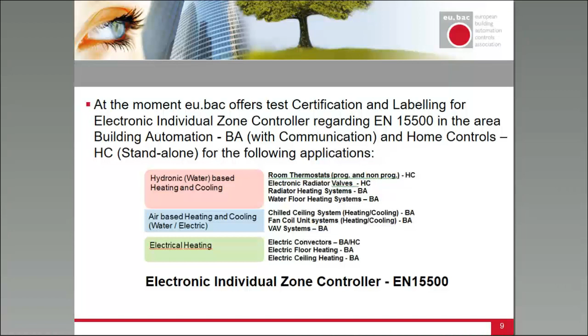In our certification, we test the controller in a lab. The controller is tested in a control loop together with its corresponding sensors and its actuator. The term actuator is usually used for a valve actuator. Most systems are water-based, so energy flow is controlled by opening and closing a valve, and for this valve we need a motor or thermal actuator that drives it. The sensor is usually a temperature sensor, very often a nickel 1000 or PT, a platinum 1000 resistor.